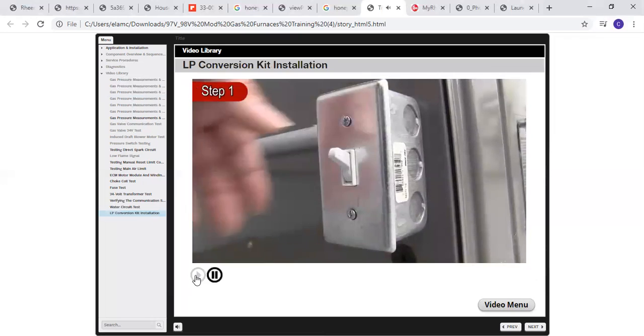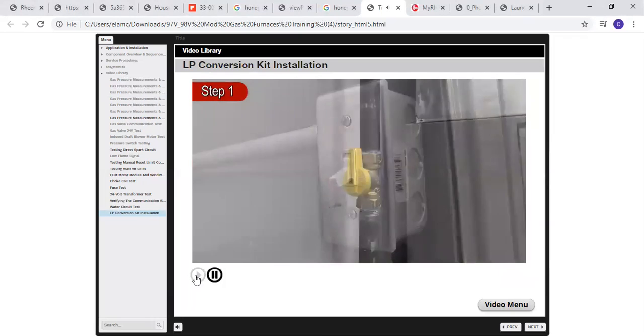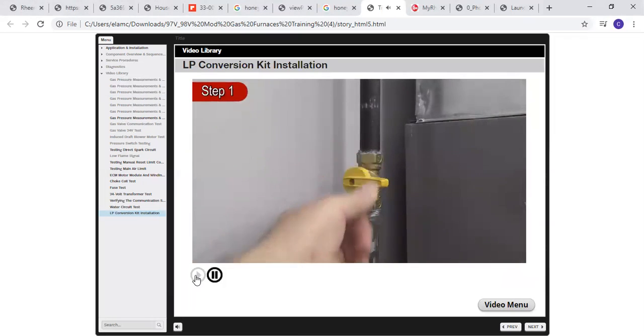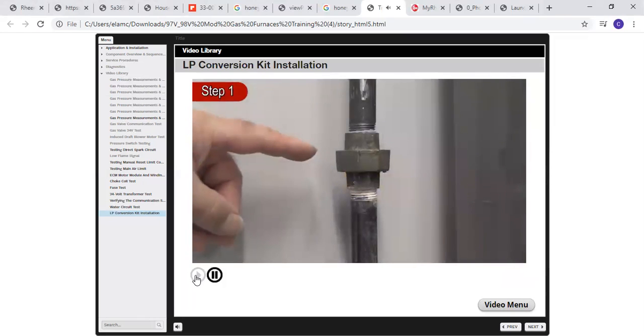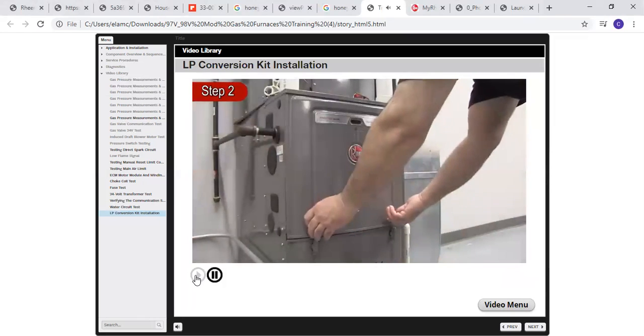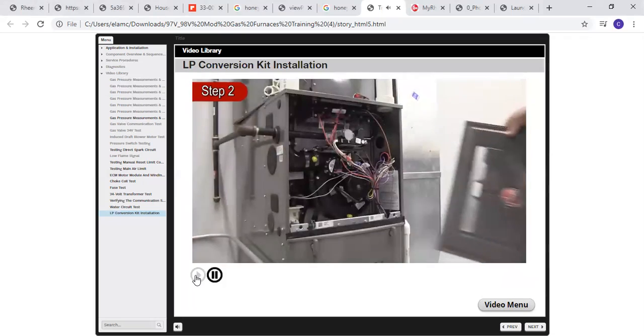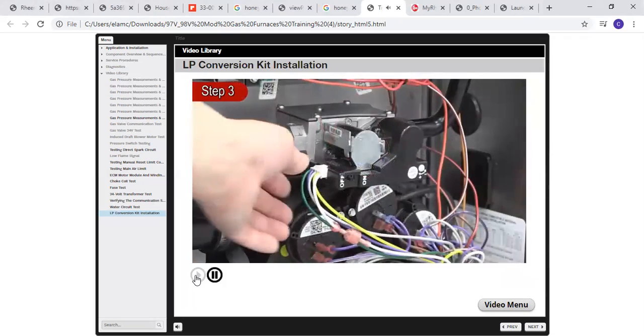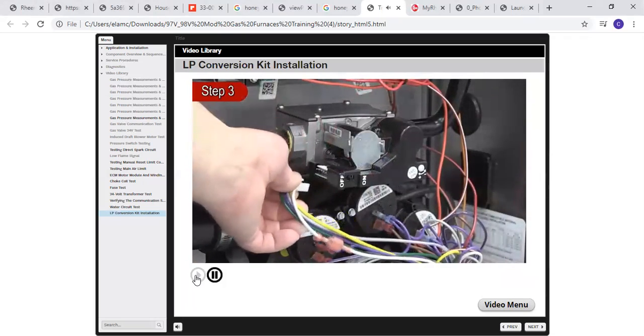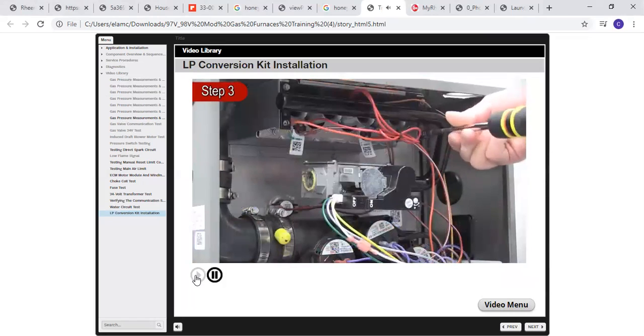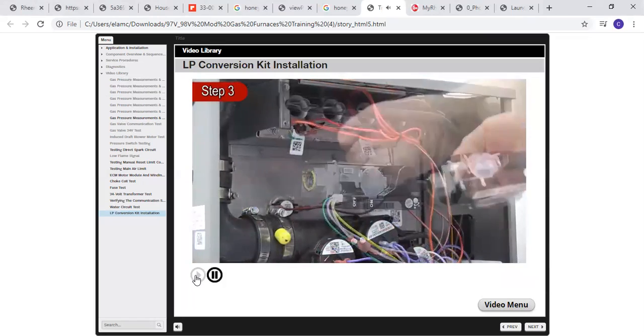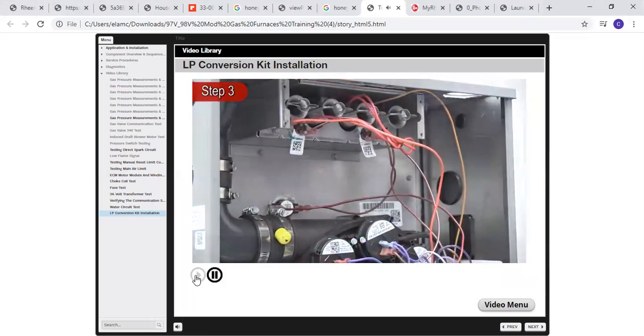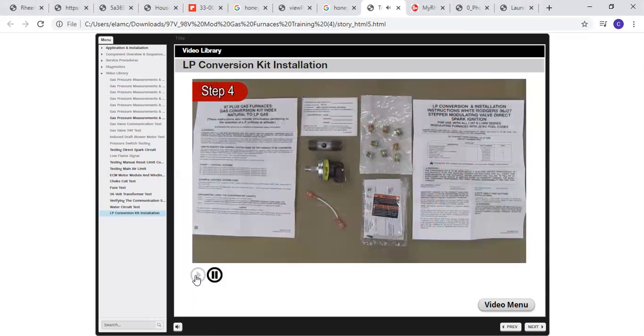Installation. Step 1. Turn off power to the unit and disconnect the gas line at the union ahead of the combination gas valve. Step 2. Remove the burner compartment access door. Step 3. Disconnect the wires from the gas valve and remove the screws that attach the manifold, and then remove the manifold assembly. Step 4. Follow the detailed instructions on the LP conversion kit to convert the gas valve to LP.